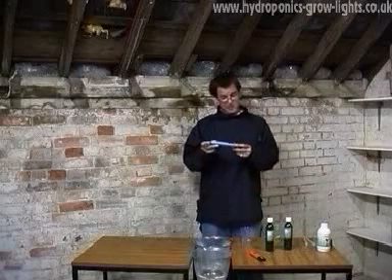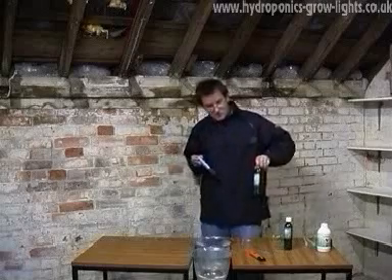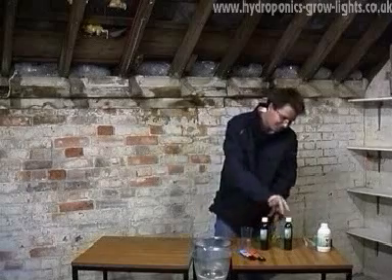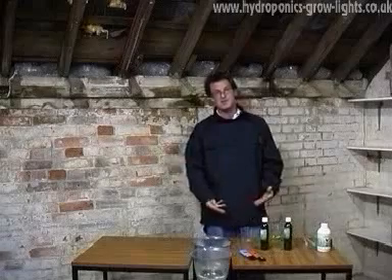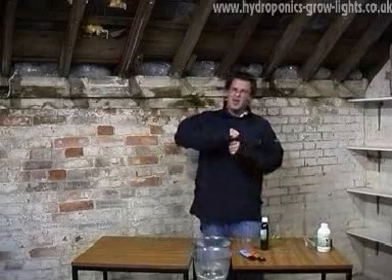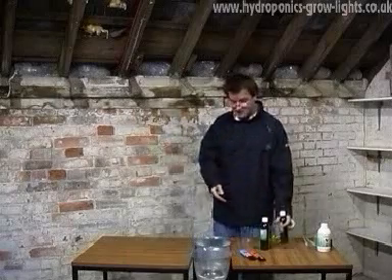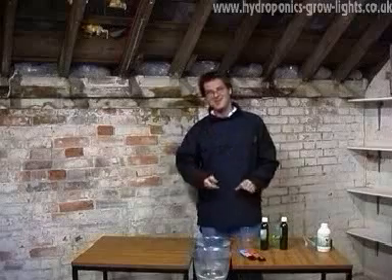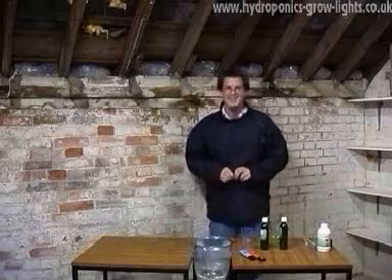A lot of people think that's very difficult, but I can't see why. Ideally, once you've used your solution in a cup, they recommend to throw it away, because the more air and the more contact it has with other surfaces, the more unstable it becomes. However, it's a bit puritanical and you can get away with pouring it back into the bottle. It's good practice to throw it away, but you can get away with not, okay? Which a lot of these fluid manufacturers won't tell you about. That's how you calibrate.